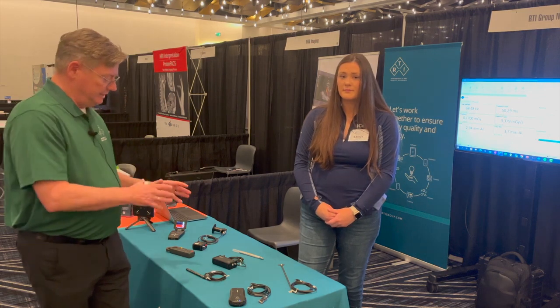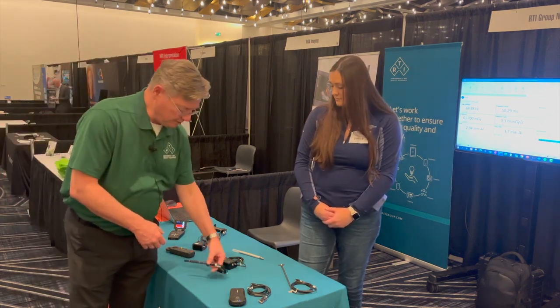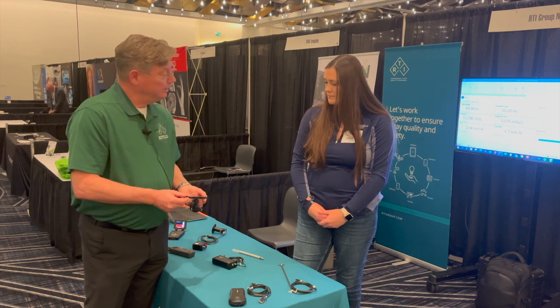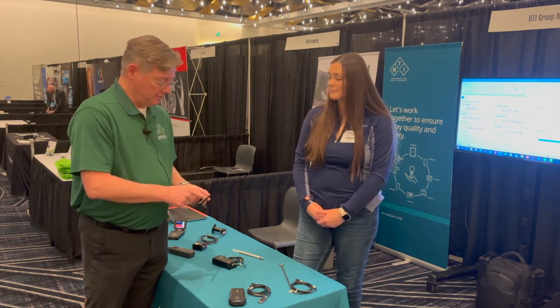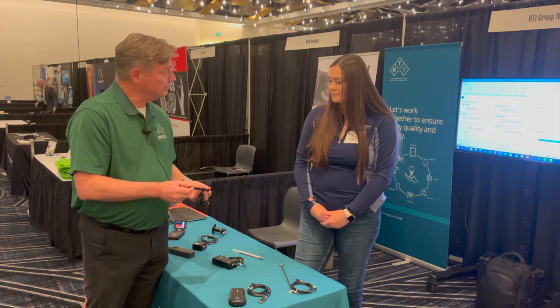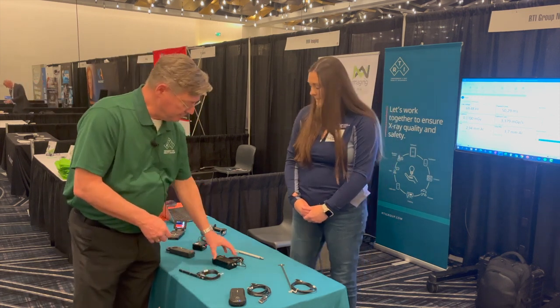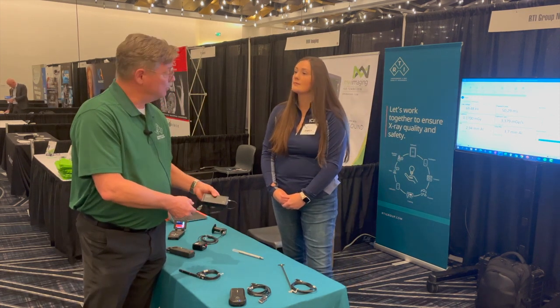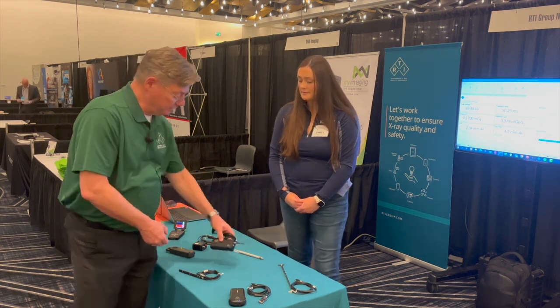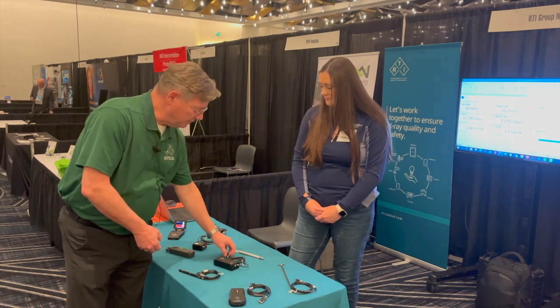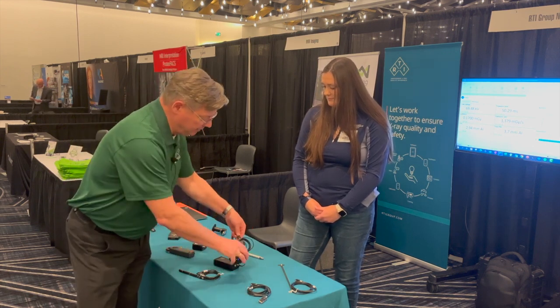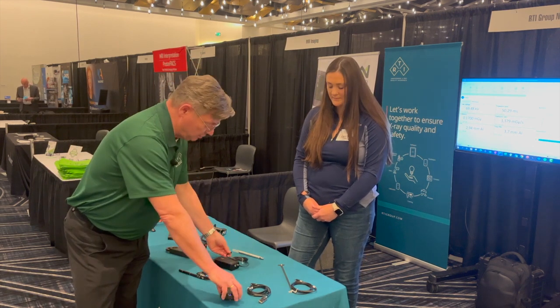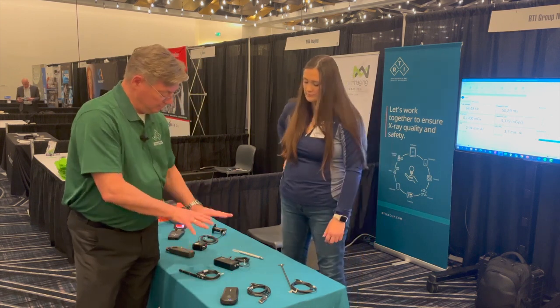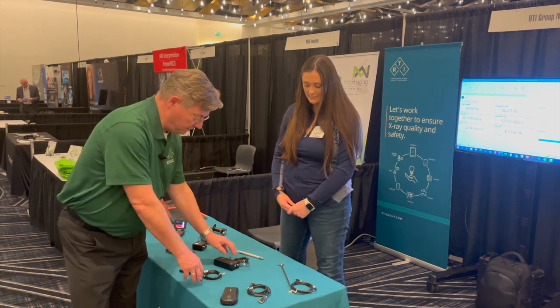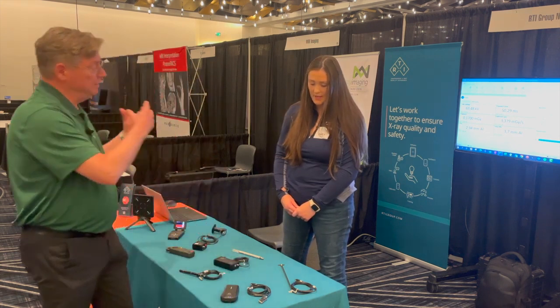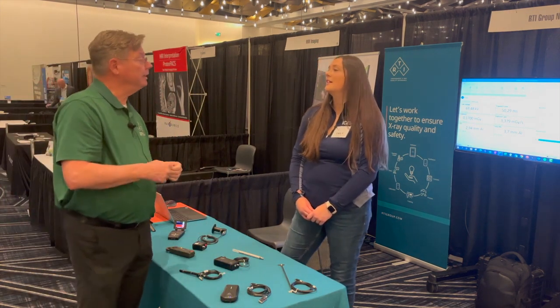For other modalities, CT for instance, of course we do have a CTDI ion chamber. Looks like this, it's a standard size, 100 millimeter, that fits into a standard phantom. It gets its bias voltage by a chamber adapter. Wow. So it connects to the chamber adapter to get the bias voltage, and the chamber adapter connects back into the Piranha, like so. Okay. So it will fit on the CT couch. This would be in the phantom, this would be on the couch, and there would be a Bluetooth connection over to your laptop. That makes a lot of sense.